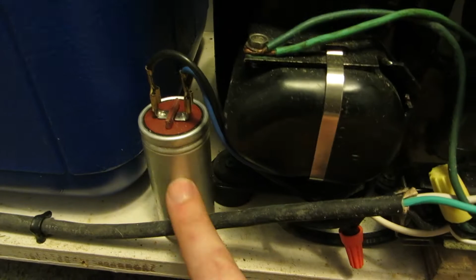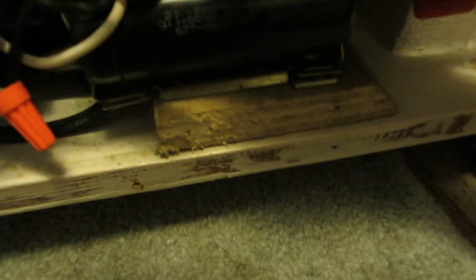Oh yeah, you got another capacitor there. That's a start capacitor, that's a run capacitor. So that's high UF - let's see, looks like 200 to 280 microfarads, 125 volts. The run one, if I can rotate it here, is 23.5 microfarads. Yeah, 23.5.